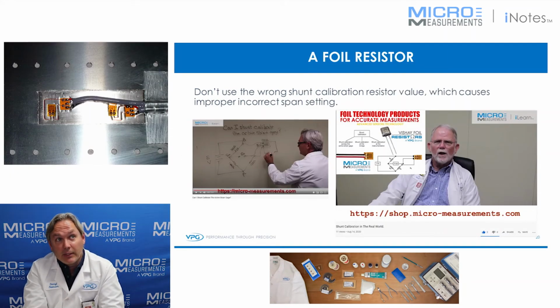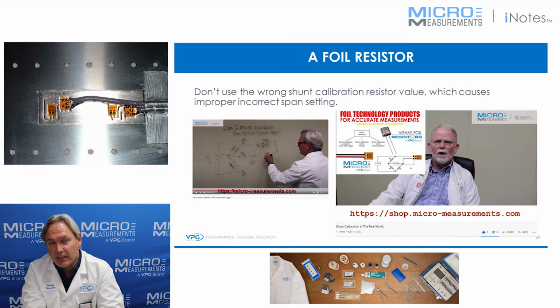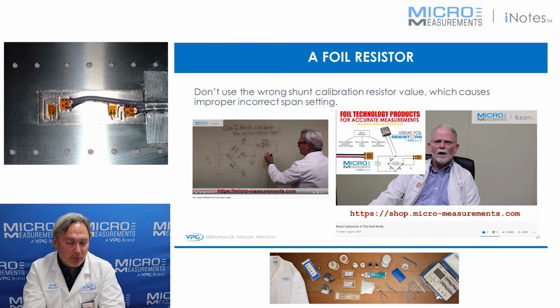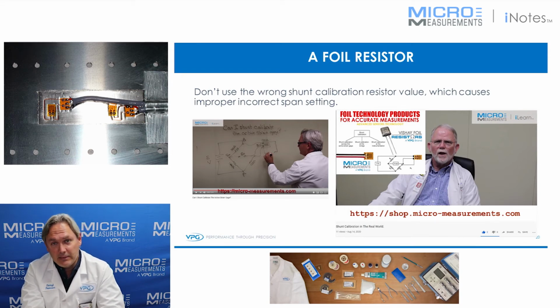Don't use the wrong shunt calibration resistor value, which causes incorrect span settings. Shunt calibration is your method to be able to set your instrumentation up and scale the output properly as a function of the strain gauge reading. So make sure you pay particular attention to what the value is and where it's being shunted in the bridge, so that you can calculate the value that it simulates, so that you can properly scale your instrumentation. Very important, and it's very easy to make errors at this location.